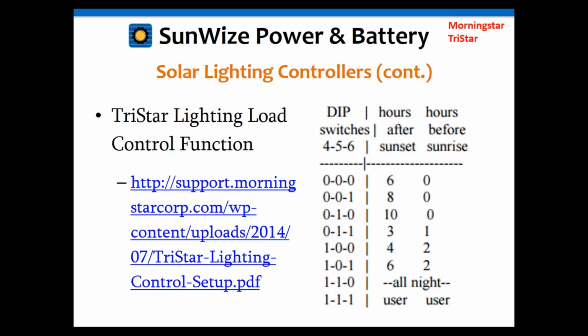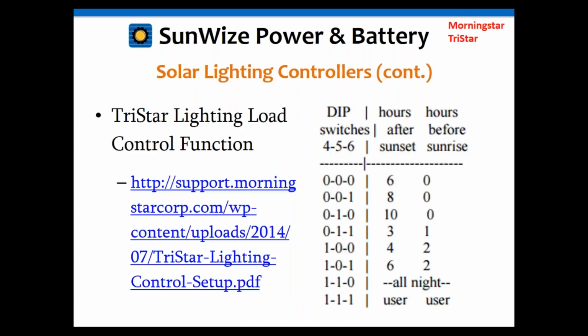So note that basically we have the same general layout structure for hours after sunset and hours before sunrise, controlled through 6 dip switch settings. And then we also have the all-night feature, the dawn to dusk mode. And then we have the last one, which is user-defined program, and that's done via either the meter add-on or via an RS-232 cable to a PC via the MSView software. We also, I forgot to mention, have a lighting control setup document published by Morningstar that goes over some of the functionality for the Tristar unit. That's both as an attachment and with a link.